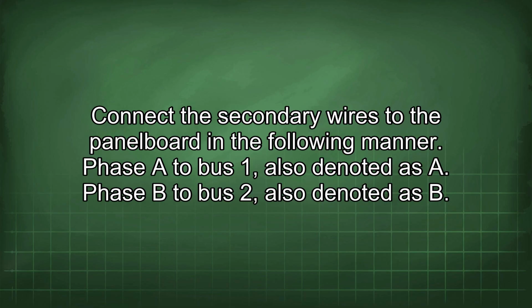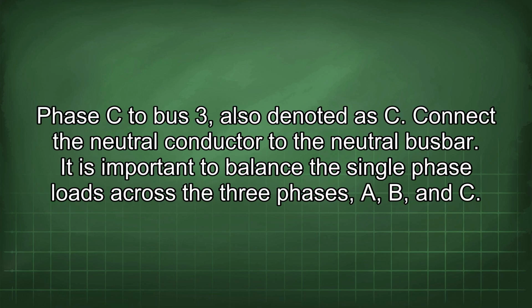Phase A to bus 1, also denoted as A. Phase B to bus 2, also denoted as B. Phase C to bus 3, also denoted as C. Connect the neutral conductor to the neutral bus bar.